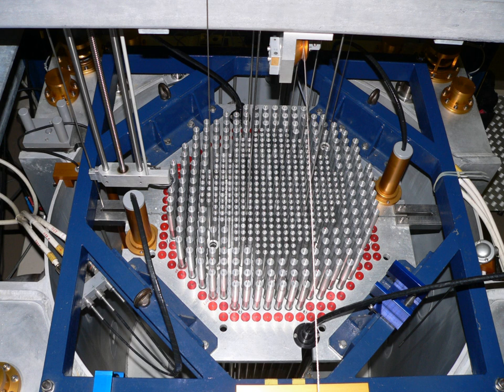Pressurized water reactors constitute the large majority of all Western nuclear power plants. A primary characteristic of PWRs is a pressurizer, a specialized pressure vessel. Most commercial PWRs and naval reactors use pressurizers. During normal operation, a pressurizer is partially filled with water, and a steam bubble is maintained above it by heating the water with submerged heaters.